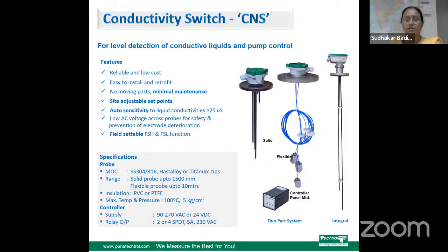Then conductivity type switch. This is basically used for conductive liquids and for level detection and pump control application. It is a reliable and low cost switch, very easy to install and retrofit. No moving parts, hence minimal maintenance. The set points are site adjustable. It is sensitive to liquid conductivities greater than 25 microsiemens. The voltage which is provided on the tip of this switch is low AC voltage, hence it prevents the electrode deterioration. You will get fail-safe high and fail-safe low functions also. The material is available in stainless steel 304 or 316, and for corrosive application, Hastelloy or titanium tips are also available.